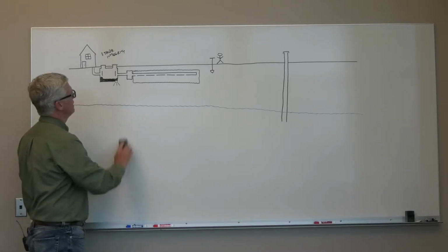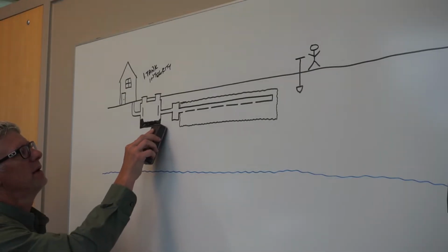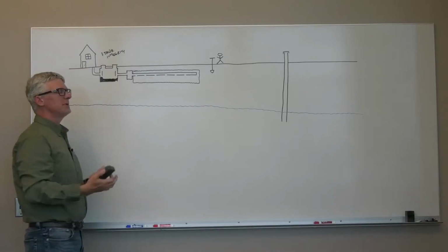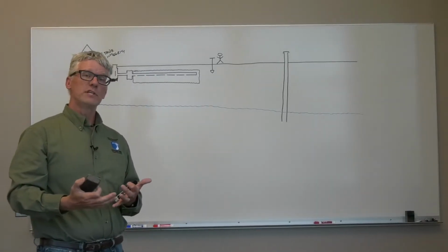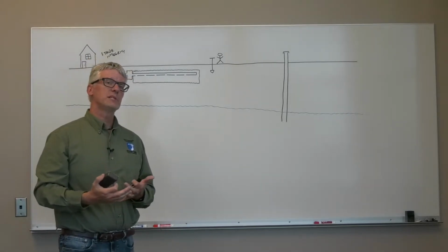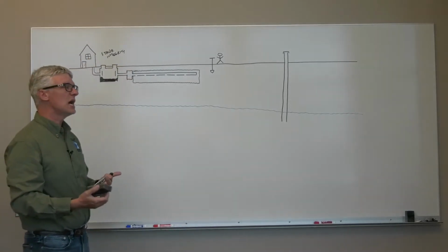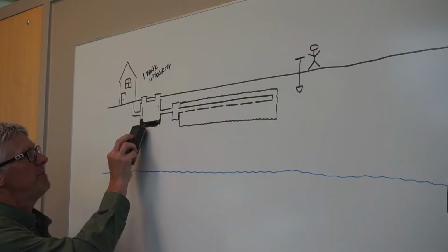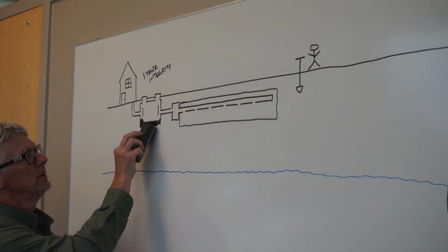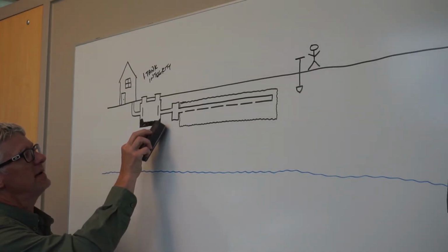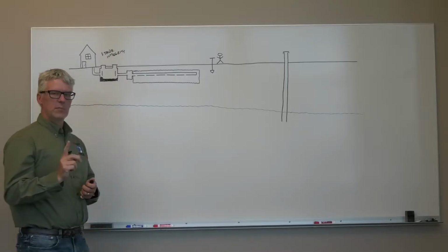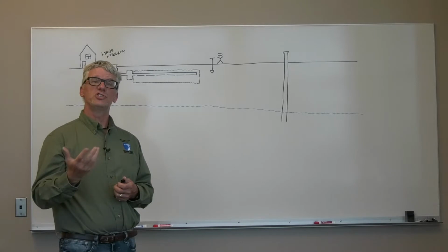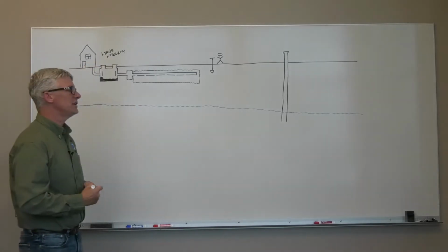The other tank integrity issue that we find quite a bit is back before septic system regulations came about in the early 70s, a lot of the septic systems in the 50s and 60s were designed with tanks that didn't have bottoms. So the tanks were not watertight. And that accomplished the first item that a septic system provides, which is disposal, but it doesn't provide any treatment.